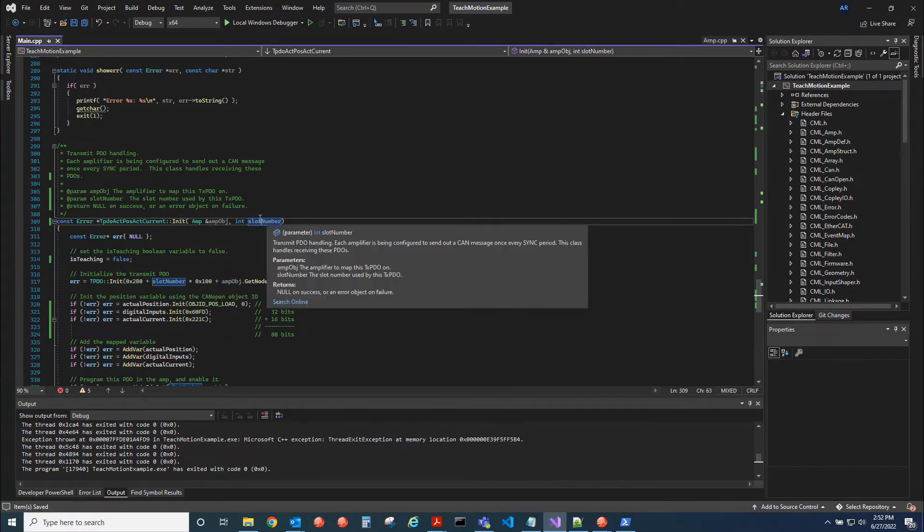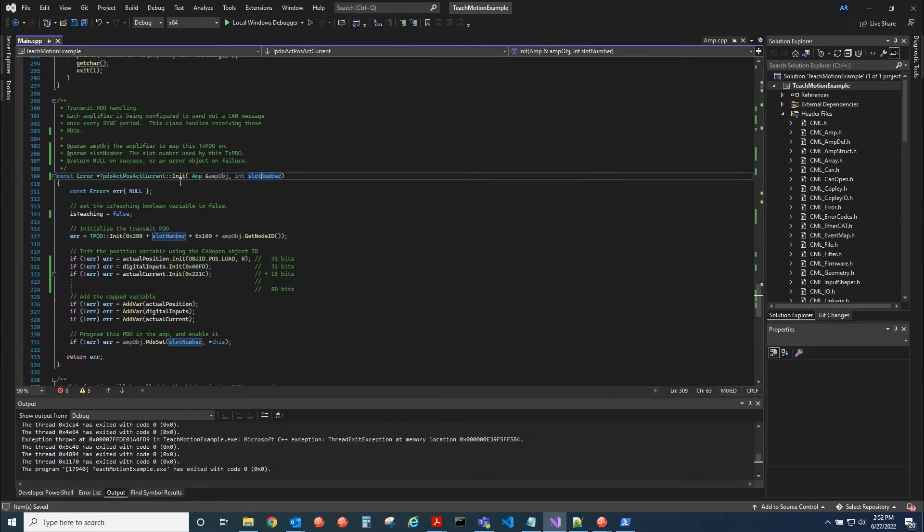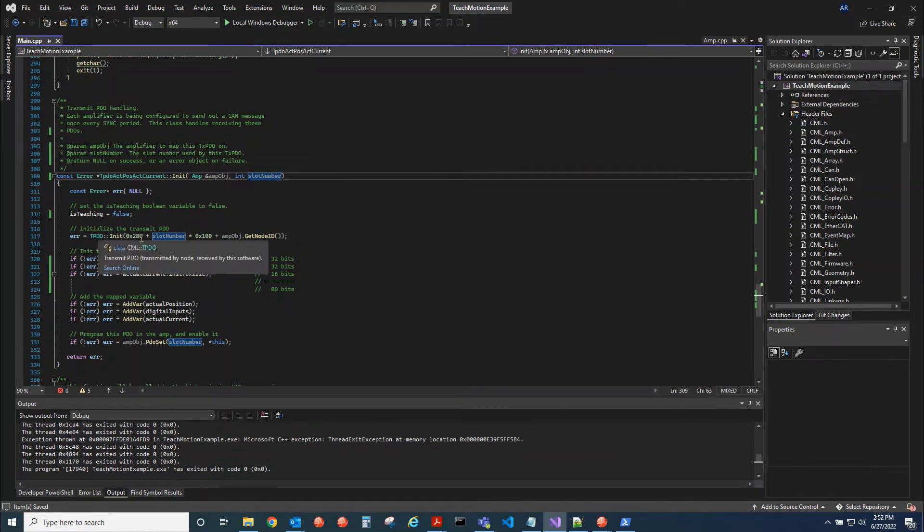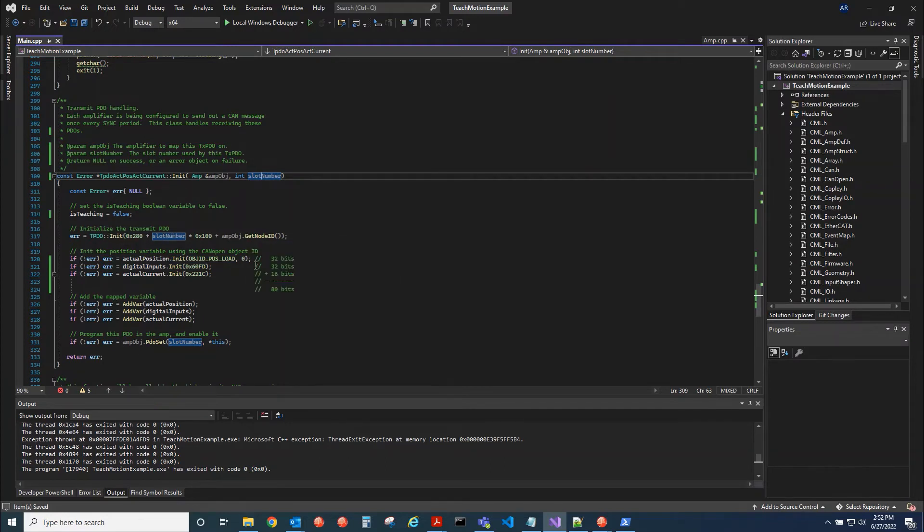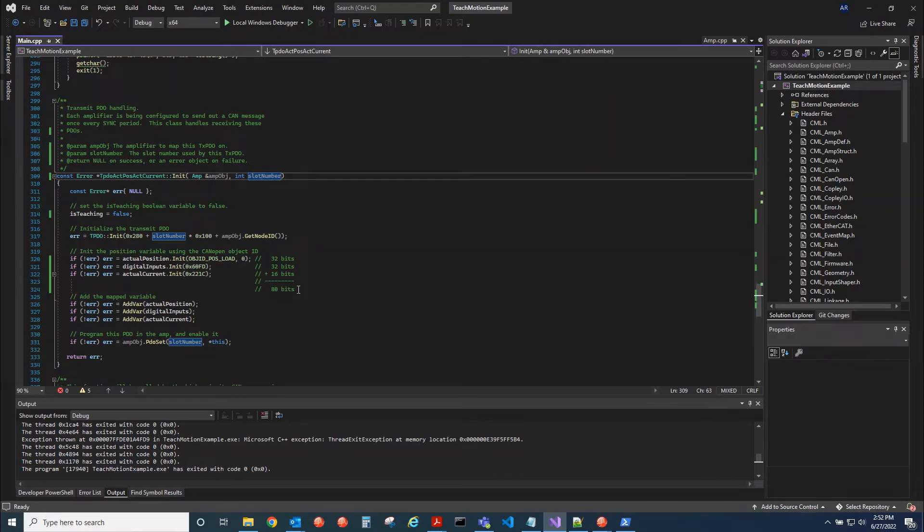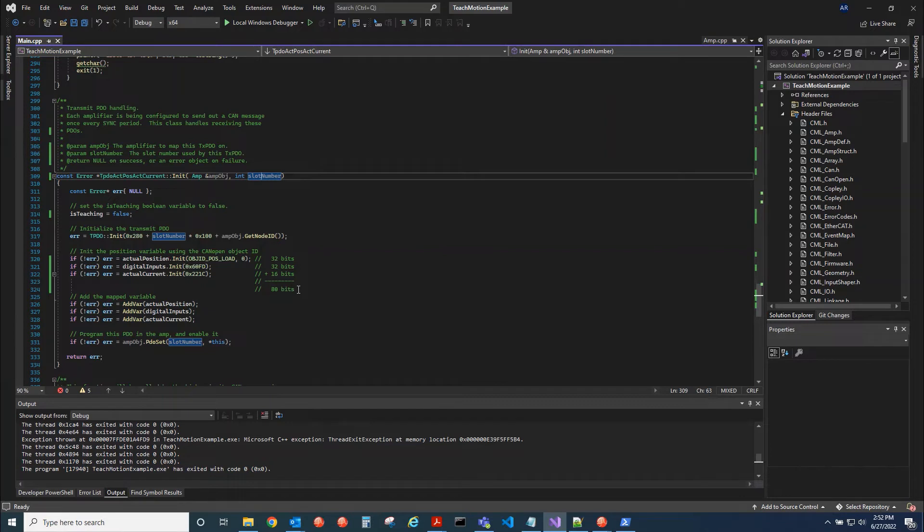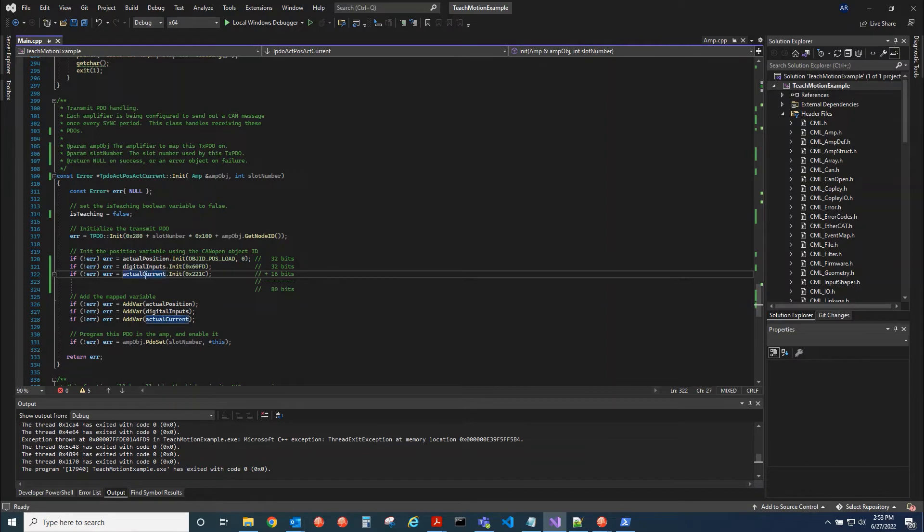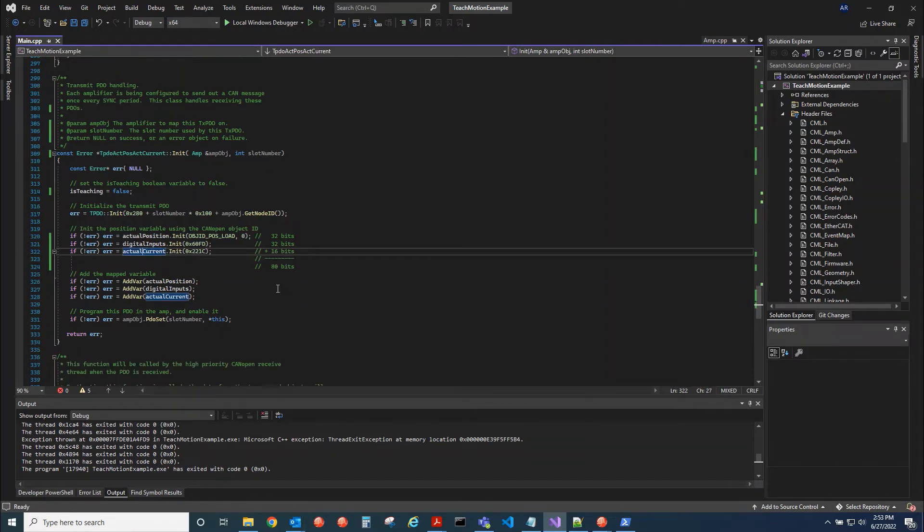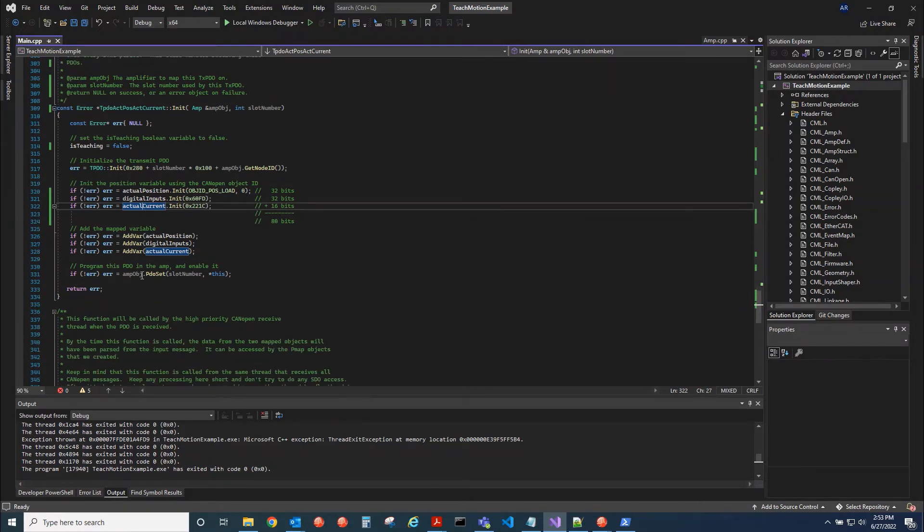So there are eight slots and we're just going to use slot number two. And so we initialize the PDO with a thing called a COB ID. It's an ID, a message ID for the network. And then we insert the objects. So for EtherCAT, you can actually put more data inside of a PDO than you could with a CAN open protocol. So with EtherCAT, I think you can get up to triple digits for your PDO mapping. So right now we're mapping 80 bits to this PDO. We have two 32-bit objects, position, digital IO, and then we have one 16-bit. So CAN open can do a max of 64, but EtherCAT can do more.